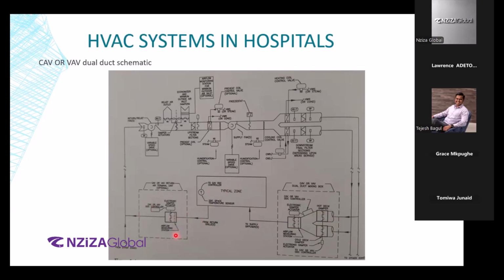What this is trying to do is maintain precise pressurization. If you modulate how much air is going out from that room as well as coming in to the room, you will have a very precise reading for pressurization. And that is exactly what we will do for the operating rooms. Operating rooms will usually have 2 VAV boxes, variable air volume boxes. One on the supply side, one on the return side, to maintain accurate pressurization, accurate controls, and accurate laminar flow for that system. Make sense?